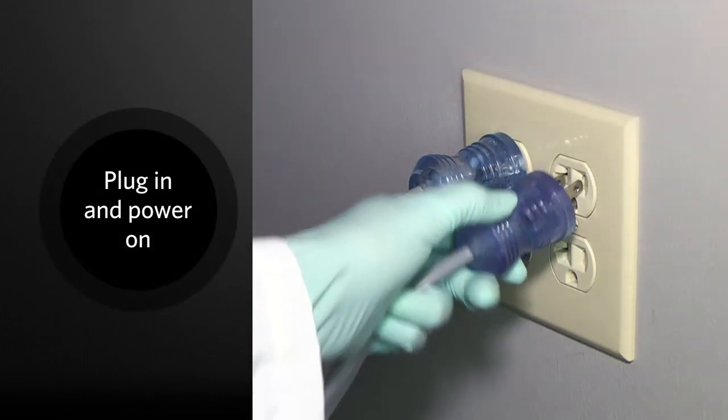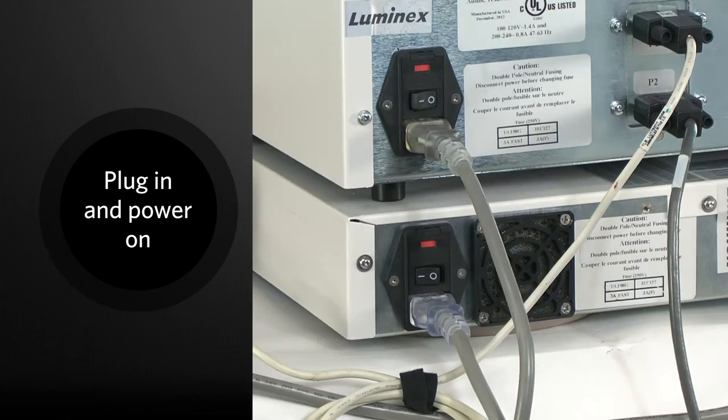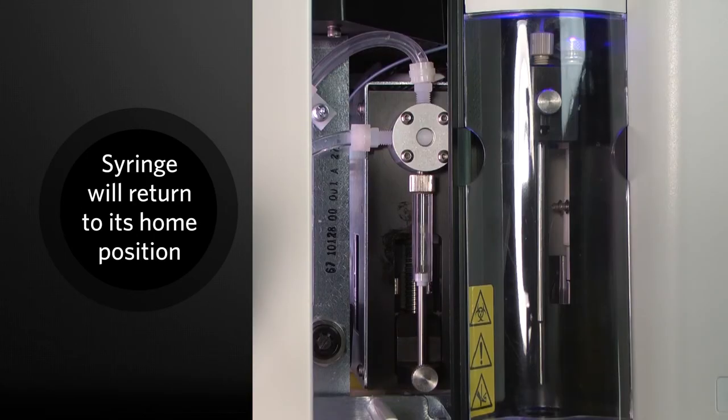The Luminex 200 analyzer can now be powered back on. The syringe will return to its home position before the analyzer begins its normal startup process.